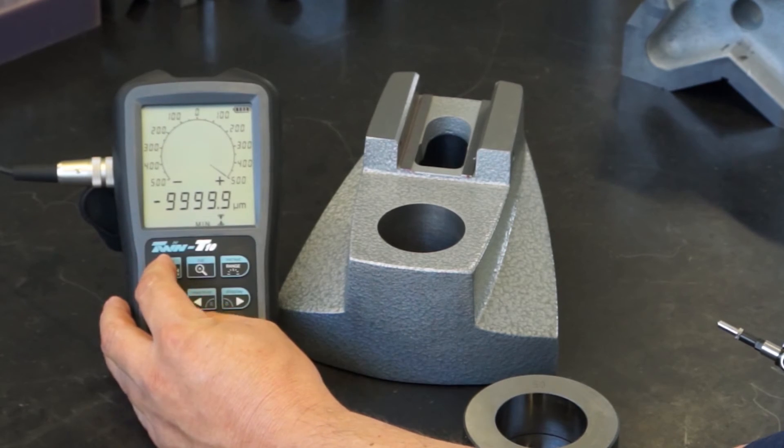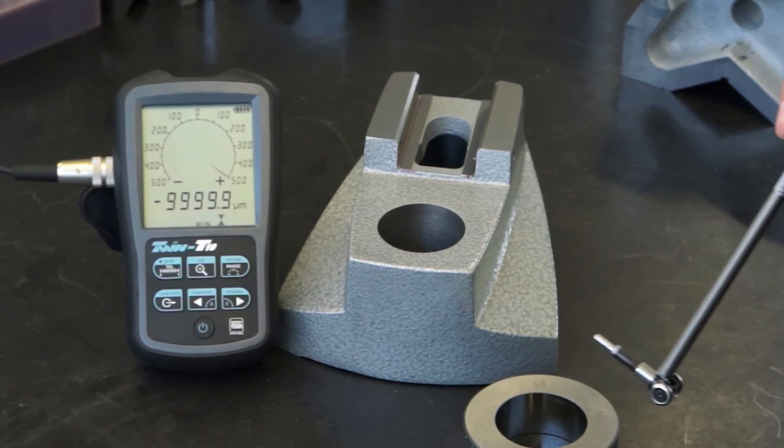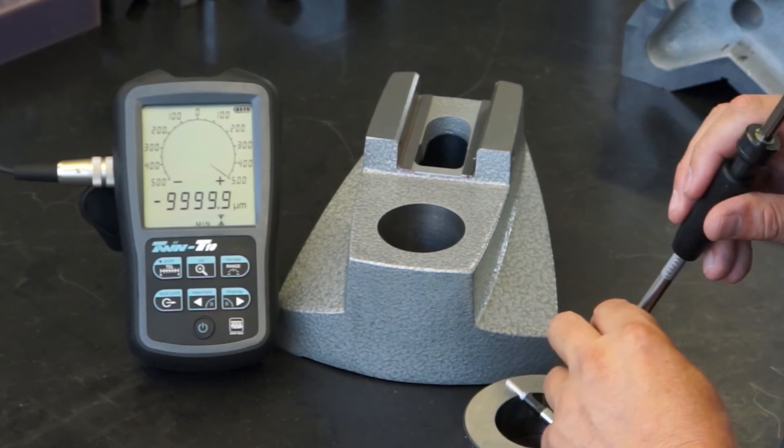Now select the min function to memorize the min value. Keep the shift key pressed and press the min key twice so the min icon appears on the display.